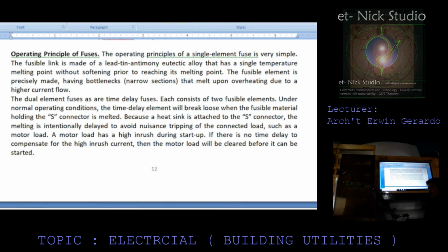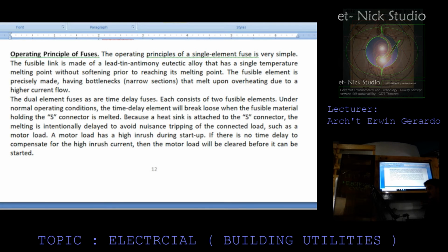Operating principle of fuses. The operating principle of a single element fuse is very simple. The fusible link is made of a lead, tin, antimony eutectic alloy that has a single melting point without softening prior to reaching its melting point. The fusible element is precisely made, having bottlenecks, narrow sections that melt upon overheating due to a higher current flow.